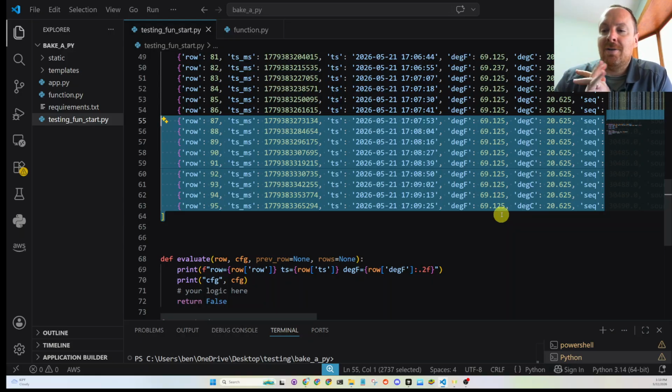And then what I want to try on the live system is this: over the past hour, what is the rate of change that the sensor saw? I think the limit is 0.15 degrees Fahrenheit per hour. If it's exceeded, we could throw a fault. The idea behind that is there could be a couple things. If it's real readings, there could be something wrong mechanically with the HVAC, or there could be something wrong with the electronics. So it's meant to do both. That's what I'm hoping to play around with.